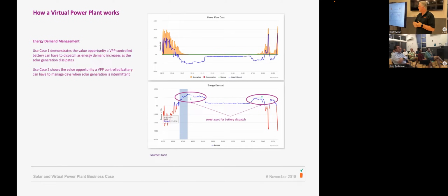So what the VPP, or virtual power plant, does is allow you to manage the batteries to offset those spikes or that pattern of demand. You can see there, when the solar drops away, the demand spikes because the solar was offsetting the grid, and that's the grid that's driving that. The other issue is like when there's a sunny day versus a cloudy day and the sun keeps peaking up, you get this up and down with your solar production, and it creates a lot of demand issues. Using the battery again allows companies and businesses to offset that.